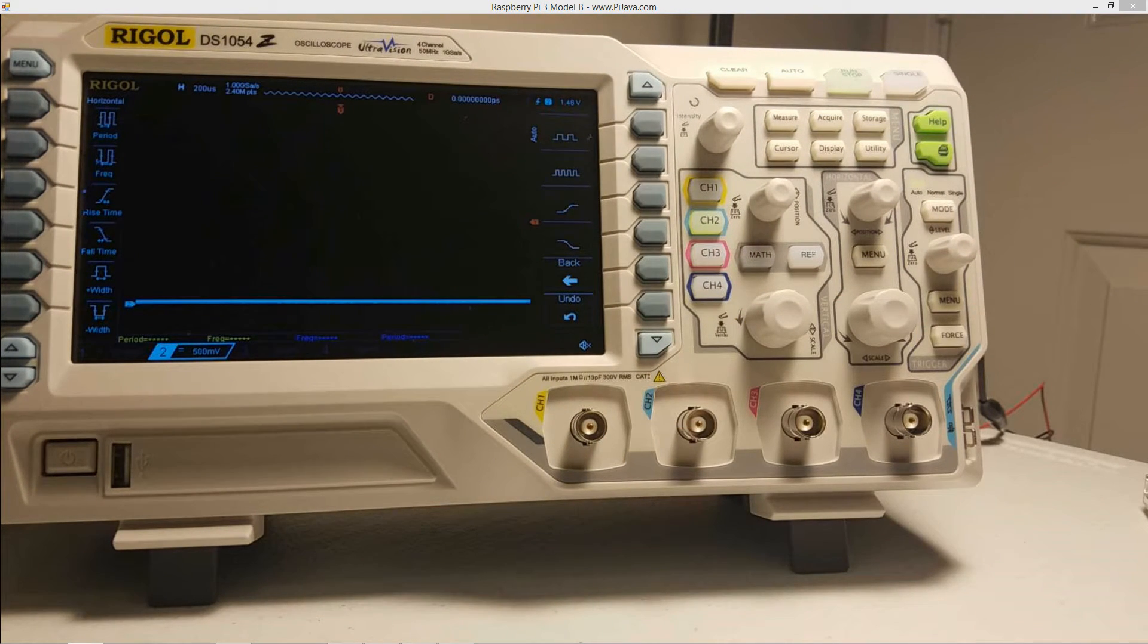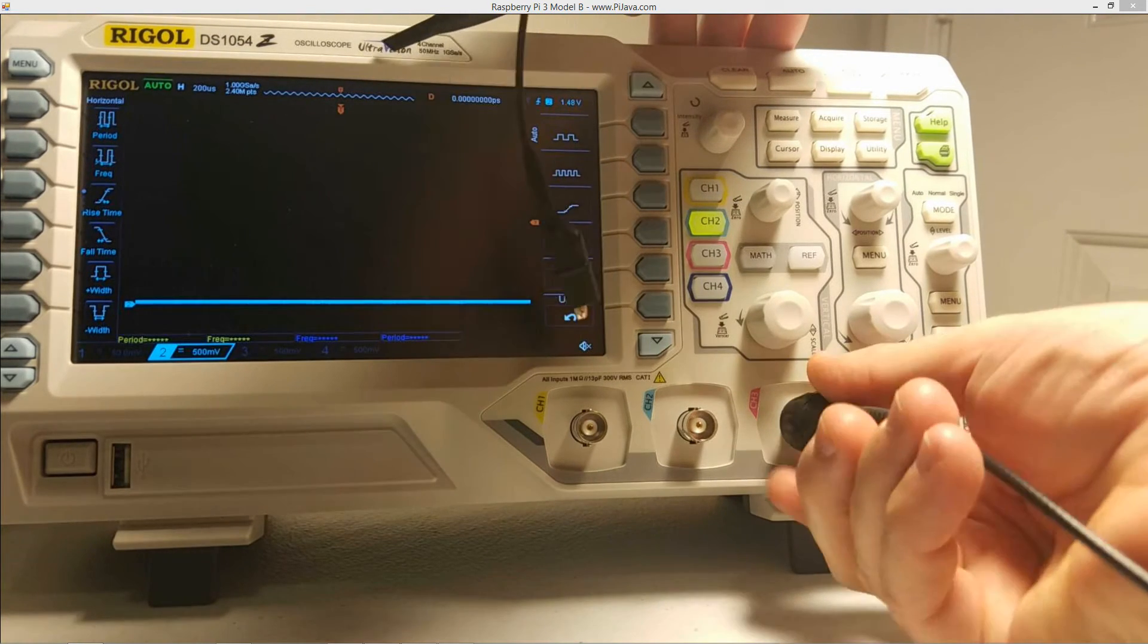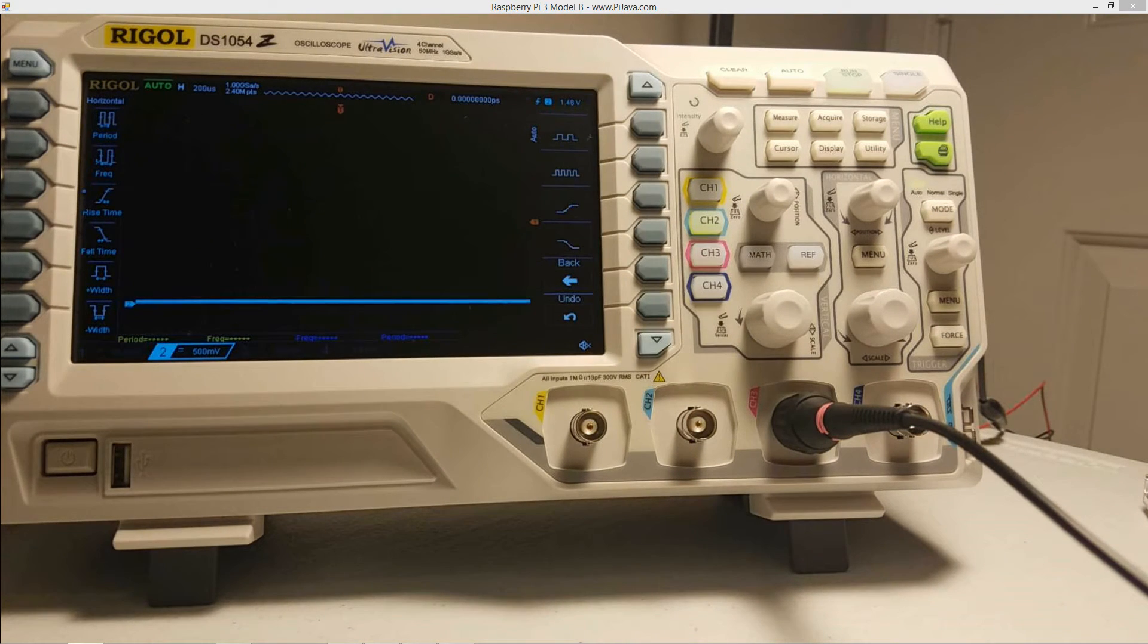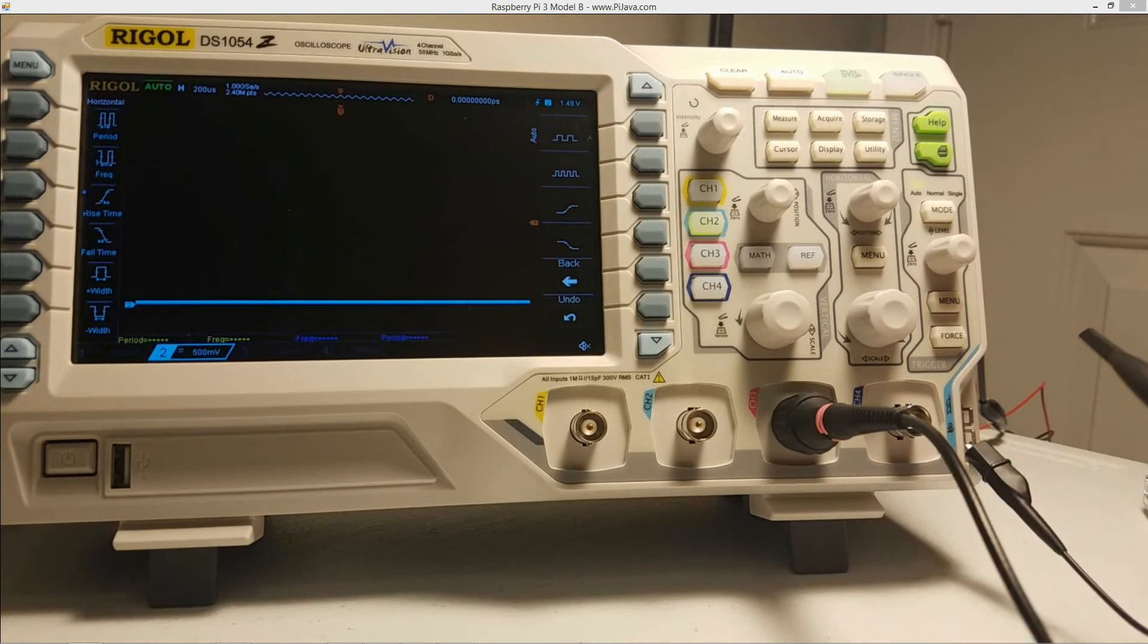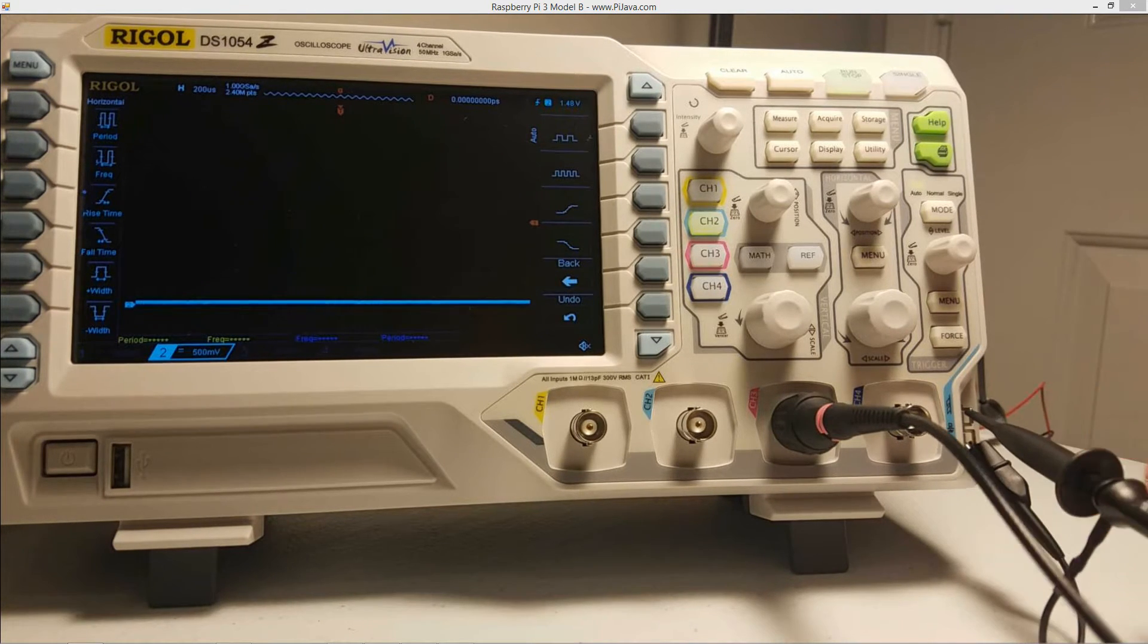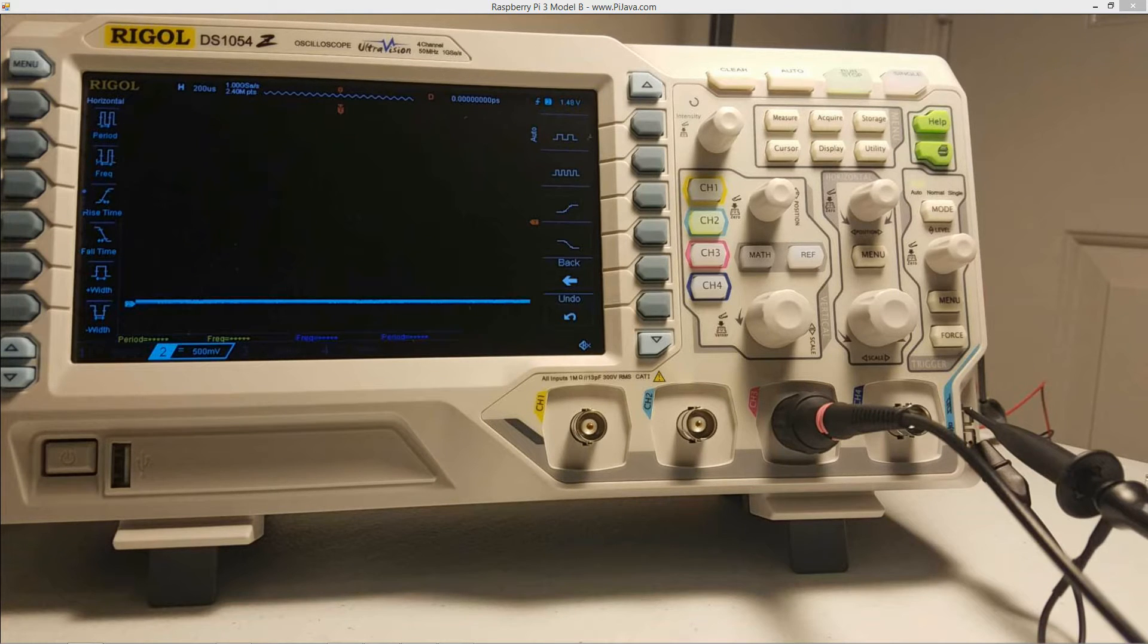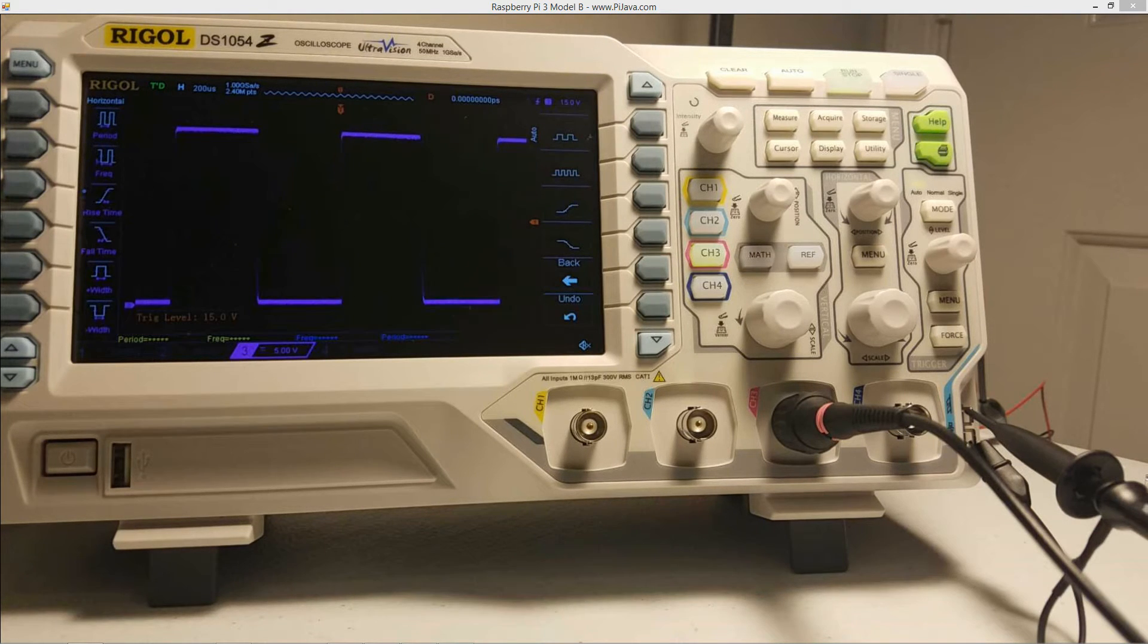So just take and put the little screwdriver in there and twist it back and forth and just, you know, make sure everything looks that I'm really happy with the results there. So that one looks pretty good. Let's go and unclip that, unclip that. I'm just going to disconnect channel two. And now let me find my pink probe. Hook it in.